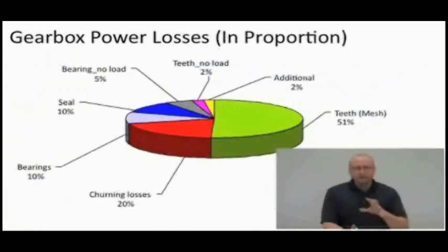If we look at the proportionality between the different losses in the gearbox, the majority of the losses come from the actual tooth contact, the meshing. And we also have churning losses, and we have bearing losses and seal losses. Seal losses can be minimized a little bit by using the correct lubrication, the correct amount of lubrication. Seals have to be lubricated. You could also use PTFE seals, which are a Teflon type of seal, and actually the seal wears away just a little bit, and some of the PTFE material is sacrificed and lays a little layer onto the shaft that it's actually sealing, which can reduce the friction a little bit.